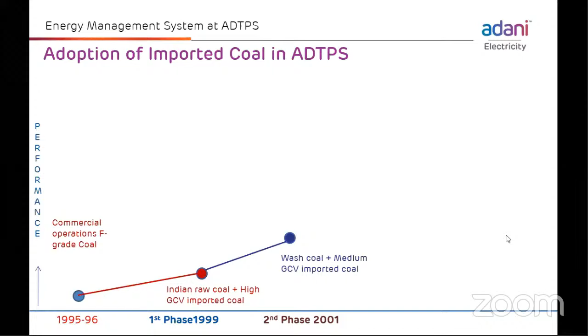In the second phase in 2001, we stopped the Indian raw coal. Instead, we established one coal washery at the coal mines in Chhattisgarh, and we wash the raw coal to reduce the ash content. And we started blending the washed coal with medium GCV imported coal. Because of this initiative, there is improvement in the plant load factor, plant reliability has increased, plant availability has improved, and there is a reduction in boiler tube leakages, equipment breakdown, and failure of CHP, that is coal handling plant, and ash handling plant auxiliaries, and thereby a reduction in auxiliary power consumption.